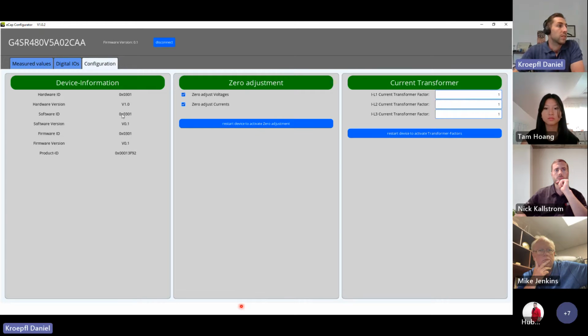In the configuration section you see all the relevant data. You can automatically adjust the voltage levels if you're sensing a certain millivolt range in your application, or do a zero adjust so it shows 0 instead of 0.004 volts. You can also manually type in any current transducer ratio - for example, for a 200 amp current transducer, you'd type in 40 and restart to activate the transformer factor. That's how quick it was; it already restarted, which is pretty cool.